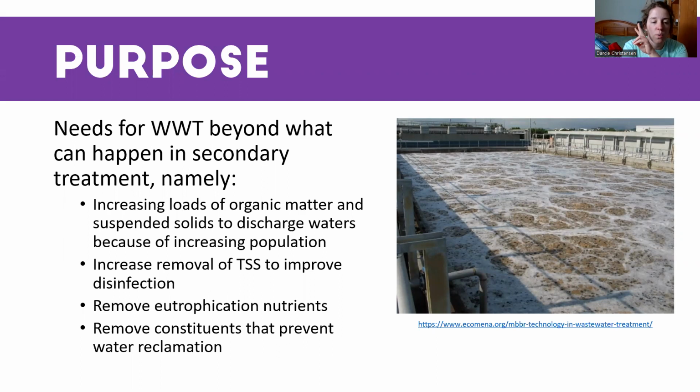Second one is that we need to increase the removal of the total suspended solids in order to improve disinfection. Disinfection, you can read and study into that. Very interesting. Disinfection is fascinating to me. But especially when we're doing UV, we need to have pretty clear water to be able to have contact with that light. If it's too cloudy, the UV won't get through, but also chlorine. If there's too much flocculation, the chlorine doesn't get to the spots that it needs to. So we need to clean it up further so that disinfection is more effective.